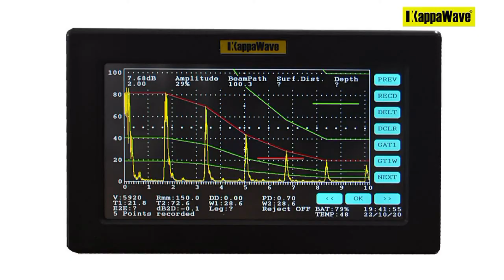Offers high sensitivity and resolution and presents sharp and unfiltered echoes. With pulse width control and echo to echo function, it offers accurate small thickness measurement ability. The machine offers a B-scan ability. A normal probe and a 37 mm Perspex block with few holes are used in this B-scan demo.